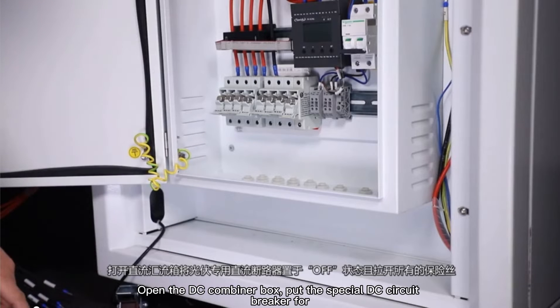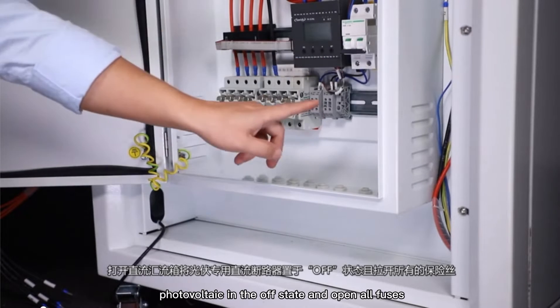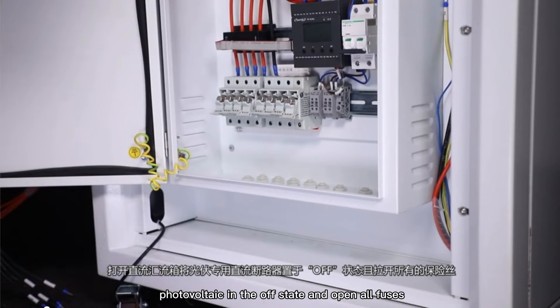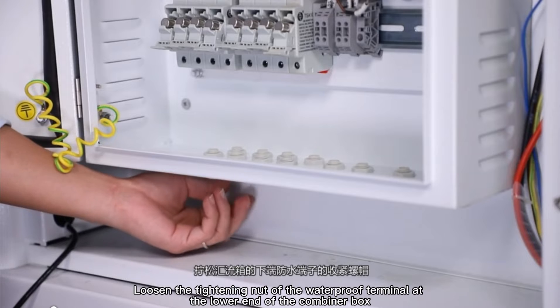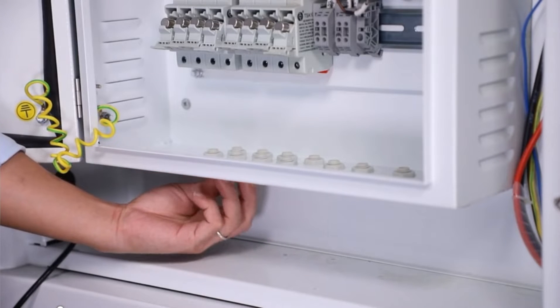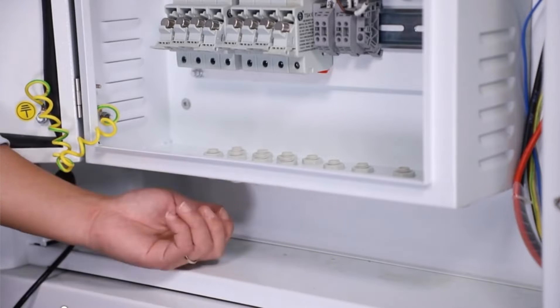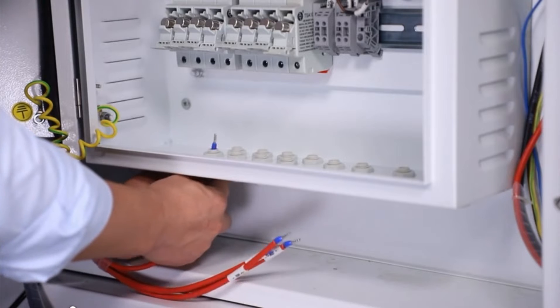Open the DC combiner box. Put the special DC circuit breaker for photovoltaic in the off state and open all fuses. Loosen the tightening nut of the waterproof terminal at the lower end of the combiner box. Put the positive and negative photovoltaic cables of the string through the waterproof terminal.